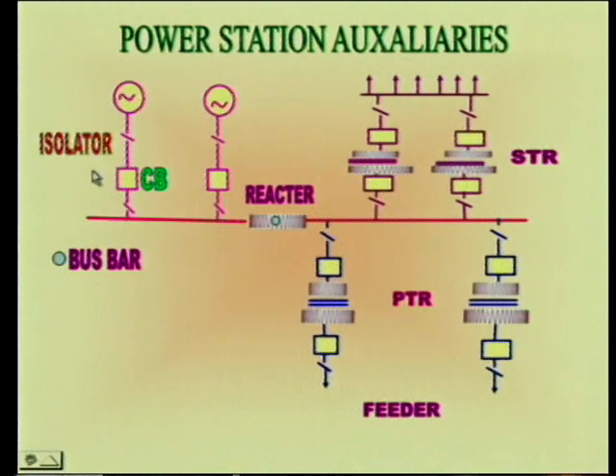Now, we have seen isolators, what the functions of isolators are, AB switches and circuit breakers. To operate circuit breakers successfully, we need relays. To make relays function successfully, we need CTs and PTs, next bus bars, reactors, station transformers, power transformers and feeders. These are a few of the auxiliaries outside of the powerhouse.